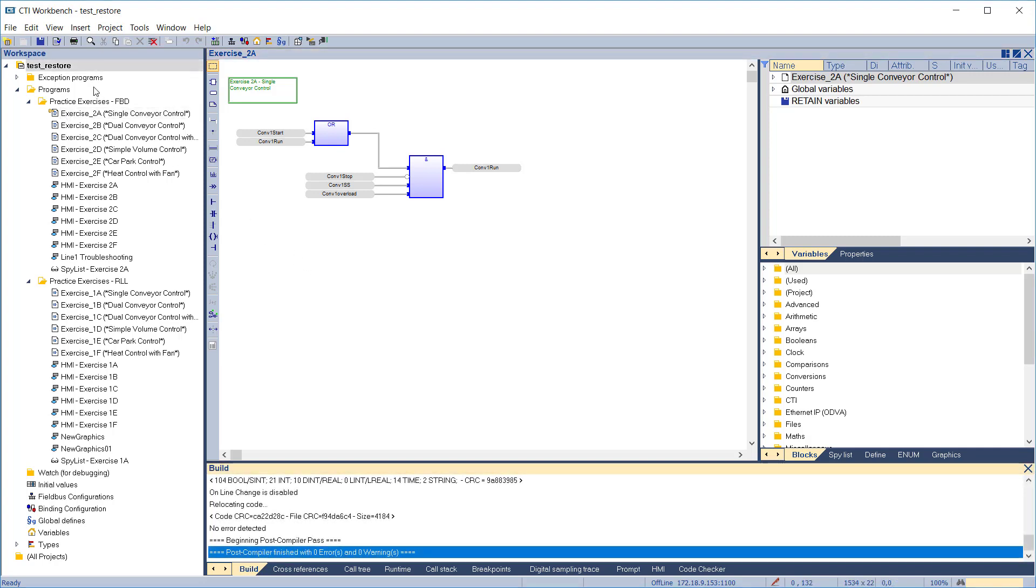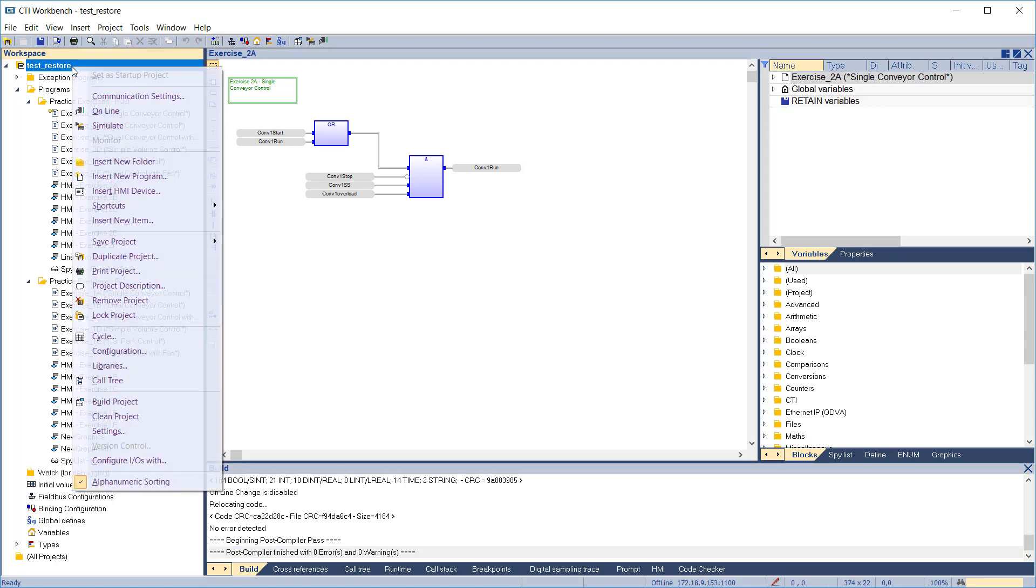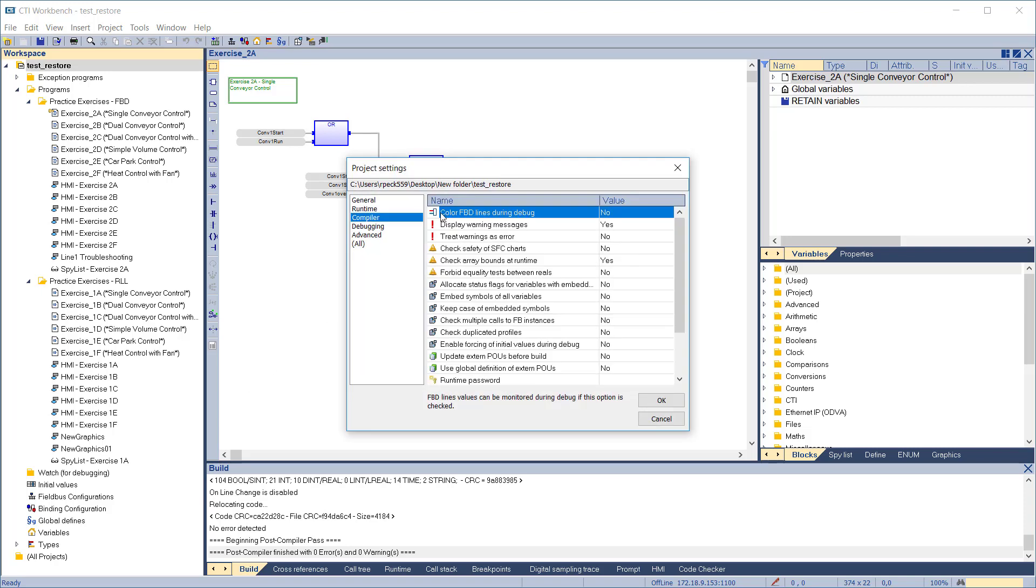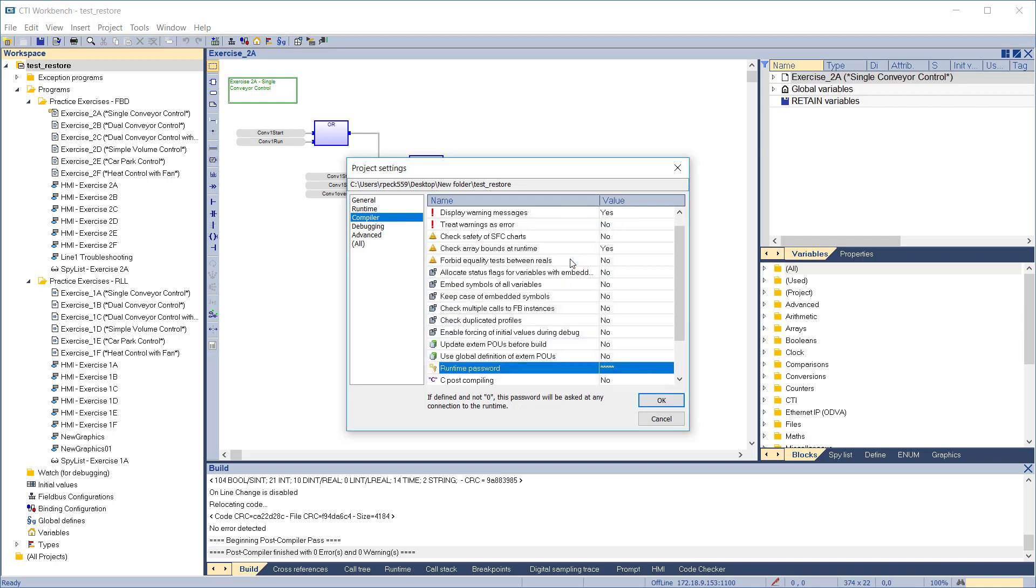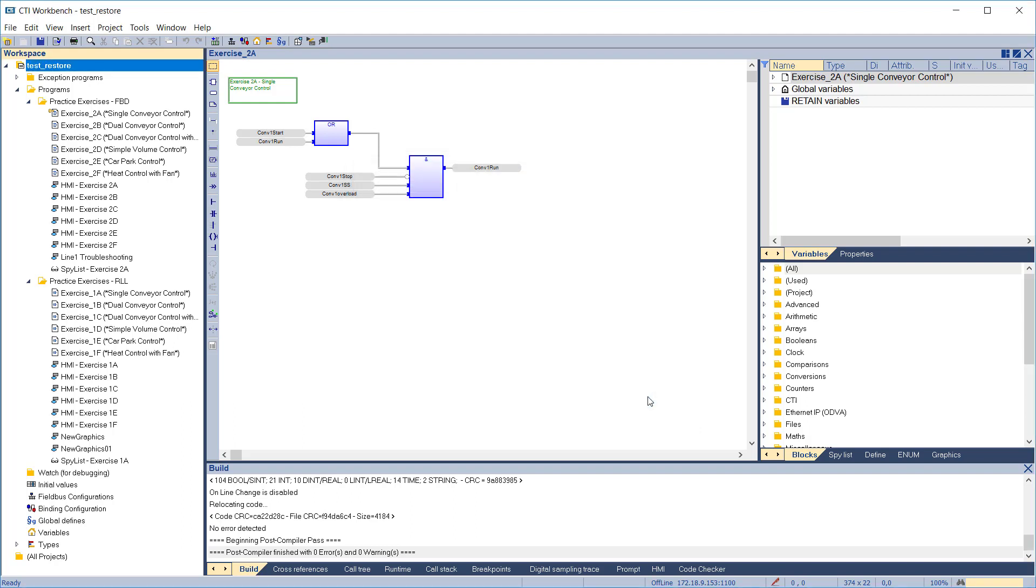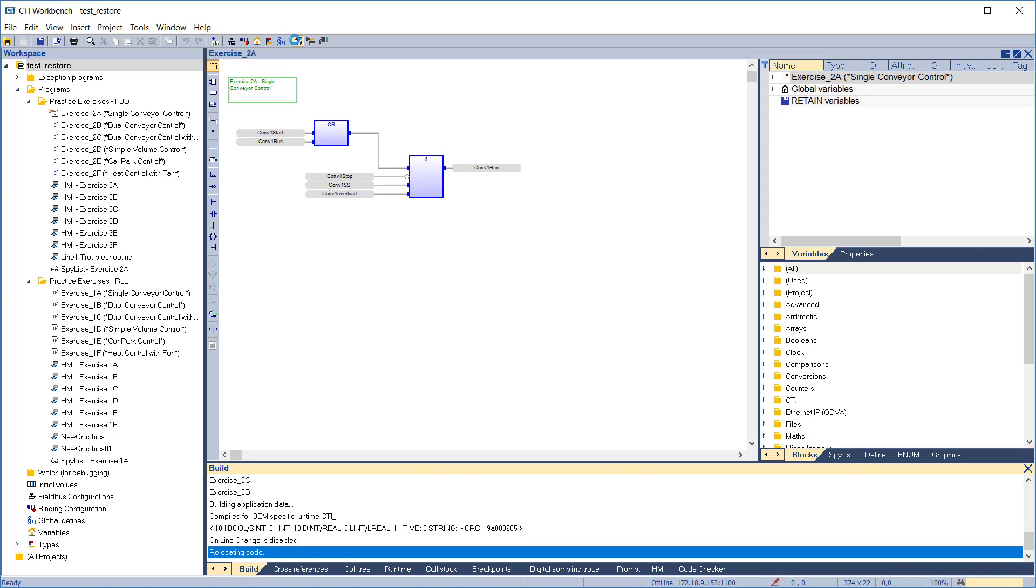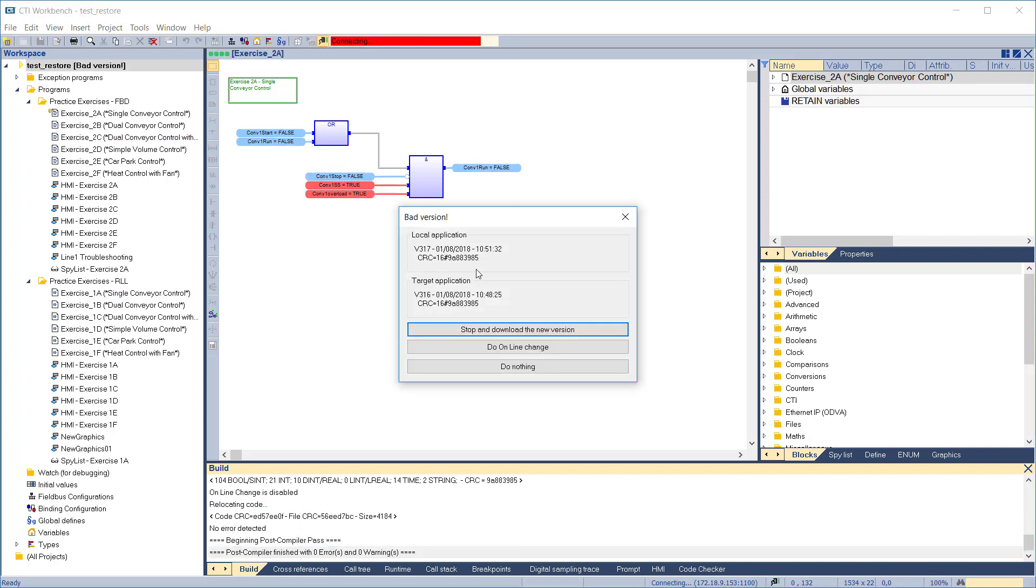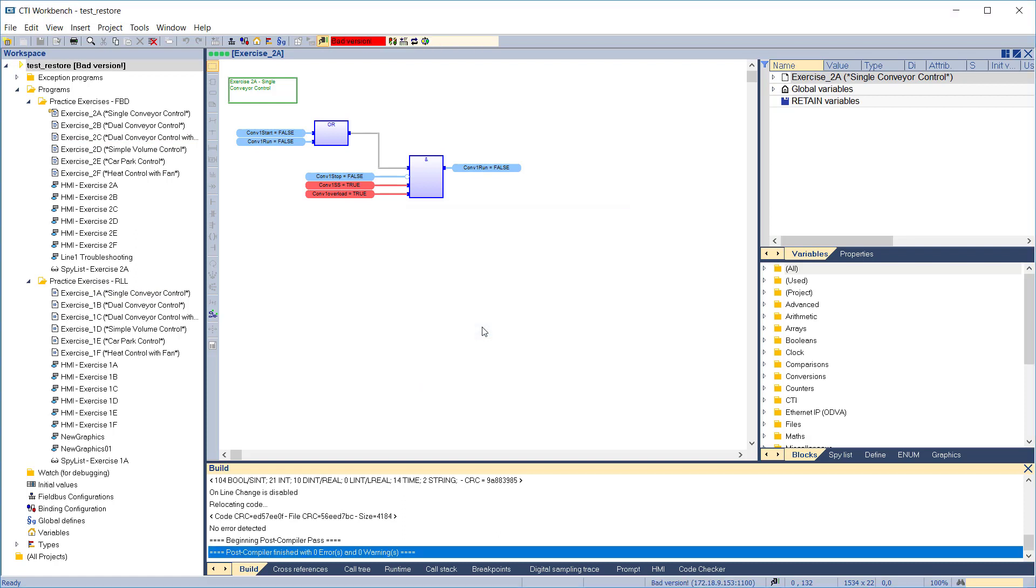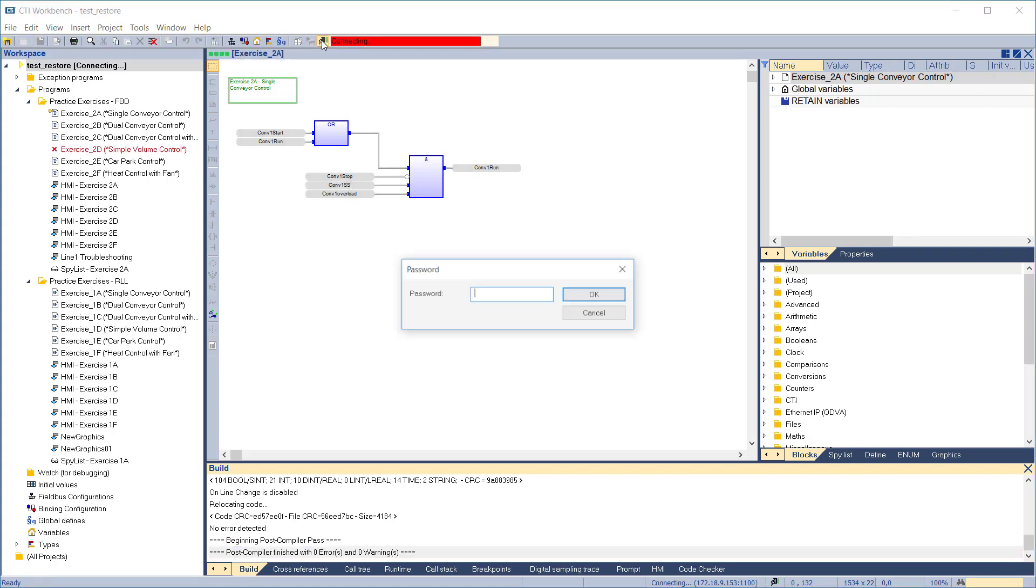Workbench includes several levels of password protection. You can protect the entire runtime system so anyone connecting to the runtime with Workbench must provide the password. To set a runtime password, right-click on the project name and select project settings. In the compiler category, double-click on runtime password. Enter the desired password and click OK to proceed. We'll compile the program, connect to the target, and download the new version. Disconnect and then reconnect. And now we're asked for the password.